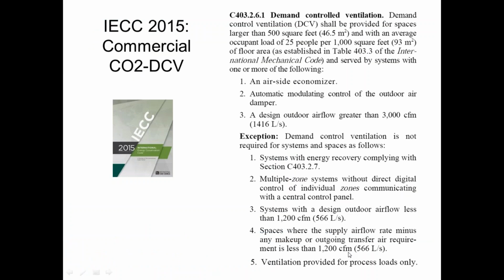Sometimes this is required by code. So when specifically is DCV required by code? The first thing to pay attention to is the density of my occupants: more than 25 people per 1,000 square feet. The old code was 40 people per 1,000 square feet, right? So now we're at 25 people. For 2012 and 2015, it's 25 people per 1,000 square feet.